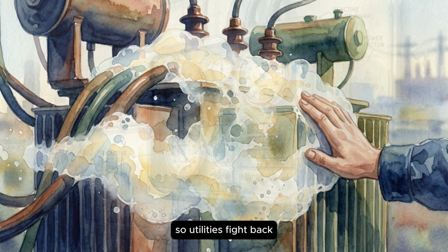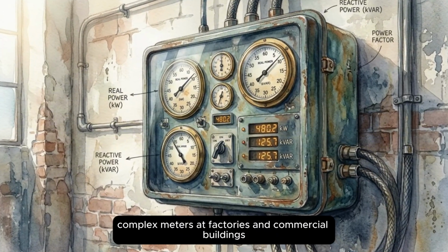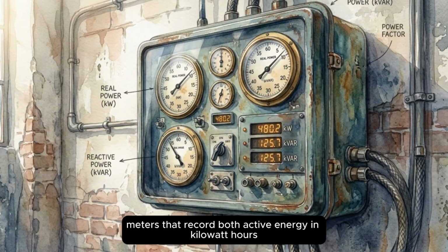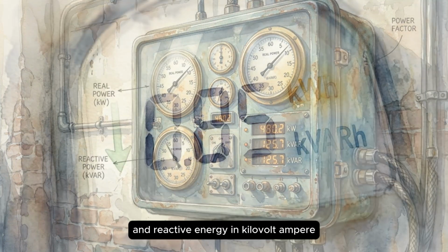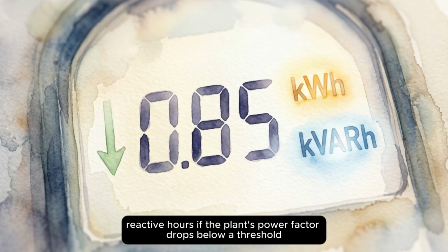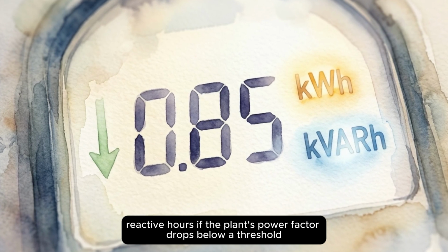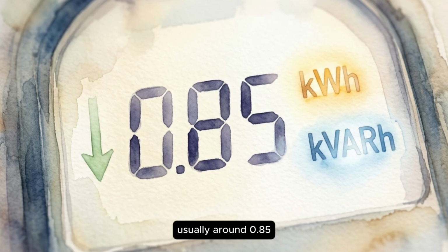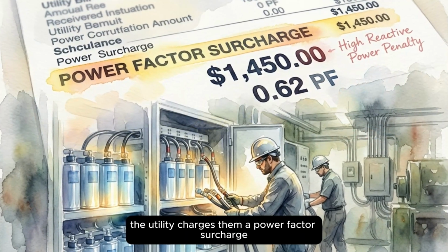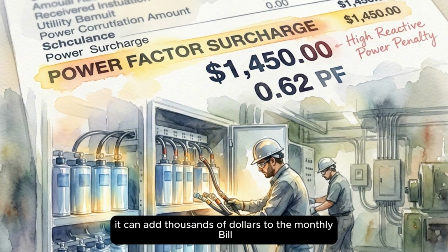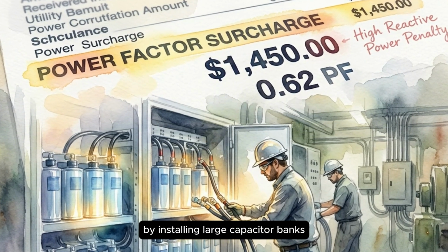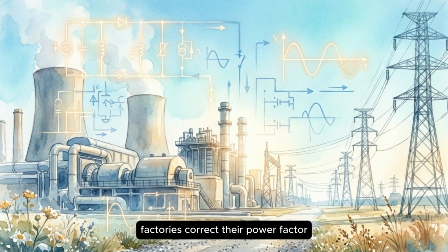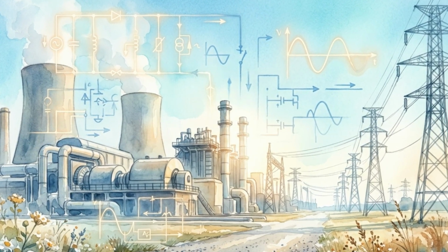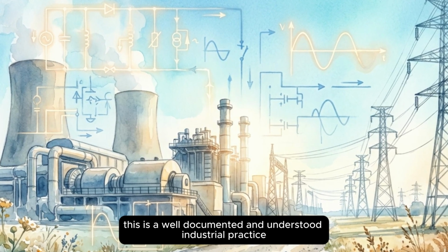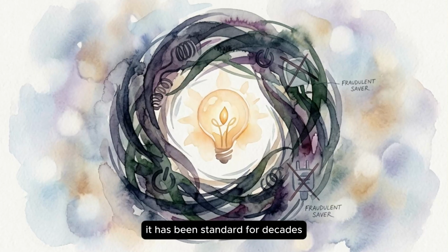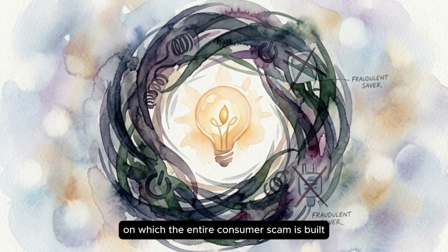The utility has to build larger cables and transformers just to handle that froth. So utilities fight back. They install specialized meters at factories and commercial buildings that record both active energy in kilowatt hours and reactive energy in kilovolt ampere reactive hours. If the plant's power factor drops below a threshold, usually around 0.85, the utility charges them a power factor surcharge, which can add thousands of dollars to the monthly bill. By installing large capacitor banks, factories correct their power factor, avoid penalties, and save real money. This is a well-documented and understood industrial practice, standard for decades, and the tiny kernel of truth on which the entire consumer scam is built.